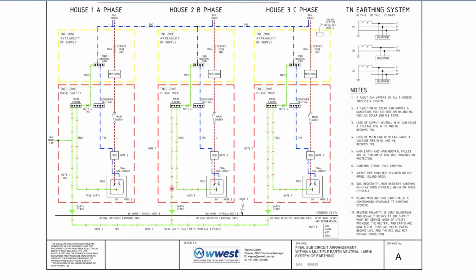So let's go back over here and we'll look at note 5, which is your main earth and your main neutral faults. They're upstream of the RCD. The RCD will provide no protection at all. And that's with all the main earth, loss of main earth, the loss of main neutral. They're up here. They're all up here, or they're all balance between your live there and your TNC neutral. And you have to have an imbalance between those two on that line there to trip the RCD.